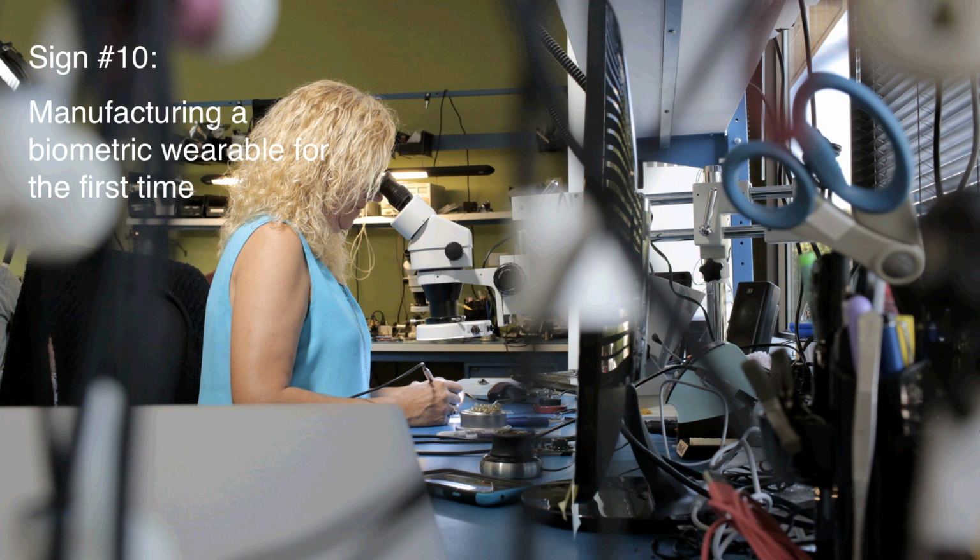And so another step that Valencell has had to take in this process is creating a test jig that sits at the end of every production line that we work with, that tests the accuracy of the optical sensor modules in those production devices, to make sure that every one of those has the same level of performance as what we saw in the lab.